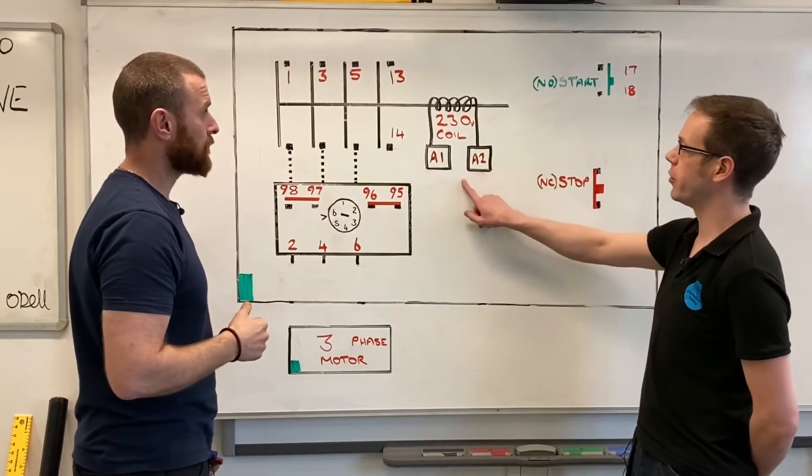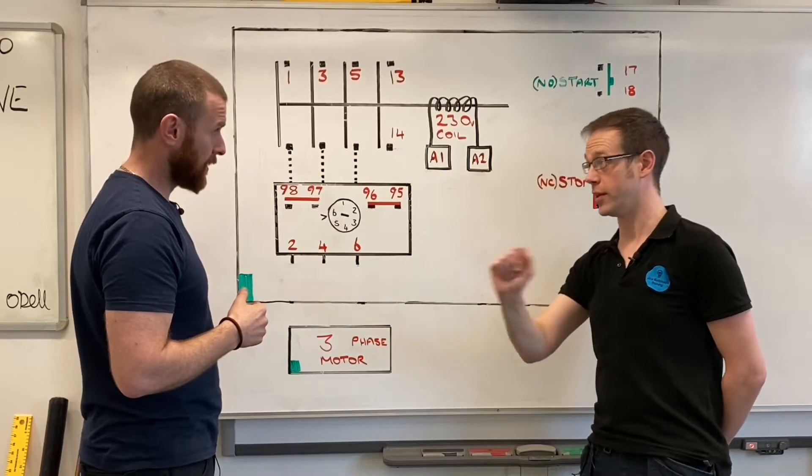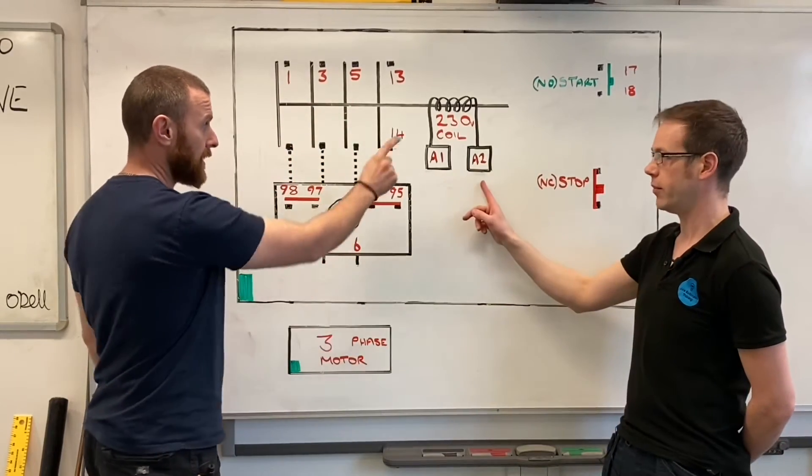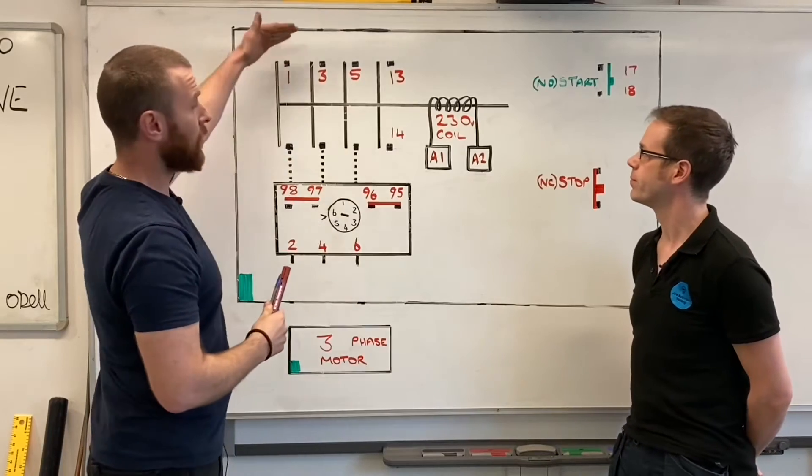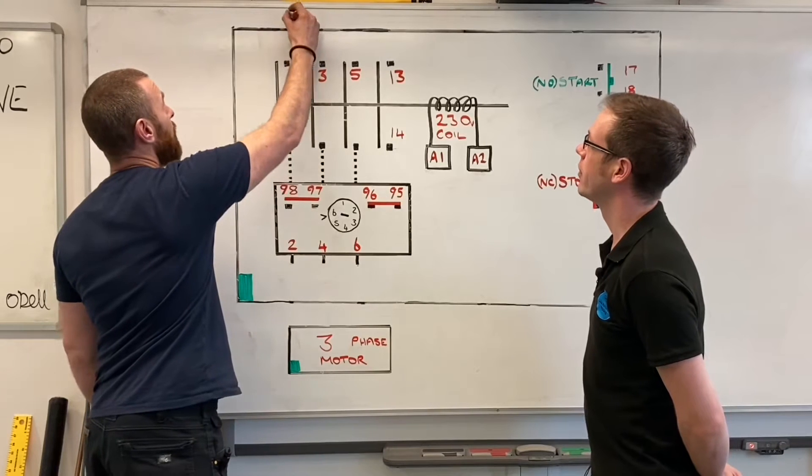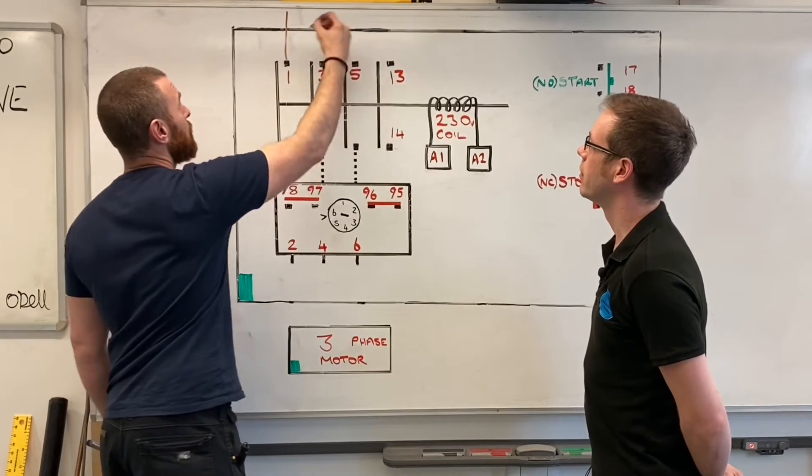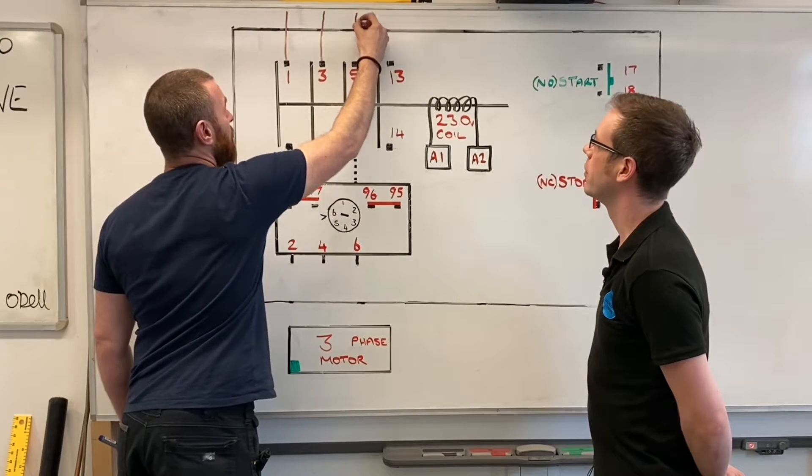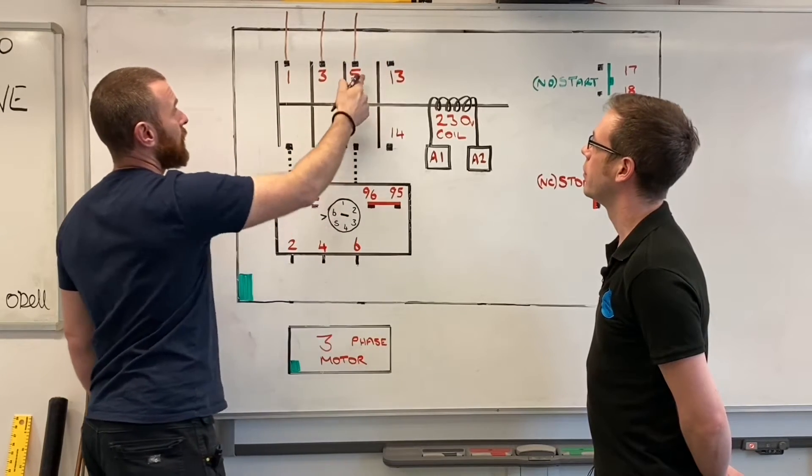Because it's a 230 volt coil, that means we're going to have to bring a neutral into this system. The neutral won't be going through to the motor, just for the supply. We'll need a neutral going through it. So if we have our three lines coming in, we have L1 coming in to number one contact, L2 coming to number three, and L3 coming to number five.